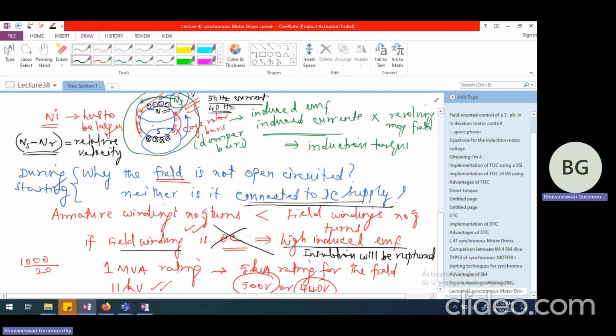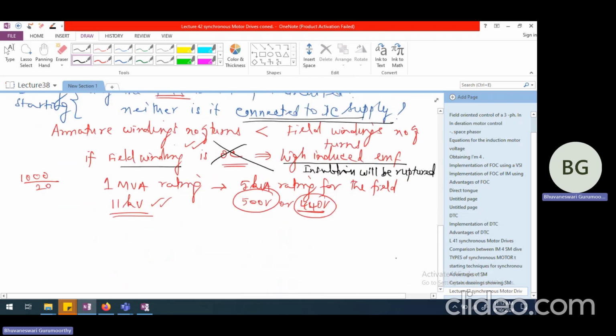So we will have different kinds of frequency currents. It is as though you are feeding the armature winding with multiple subharmonics. Due to which, we already saw that it can create oscillations in the torque. You are going to have pulsations in the torque, and some of them are going to manifest themselves in the form of braking torque.